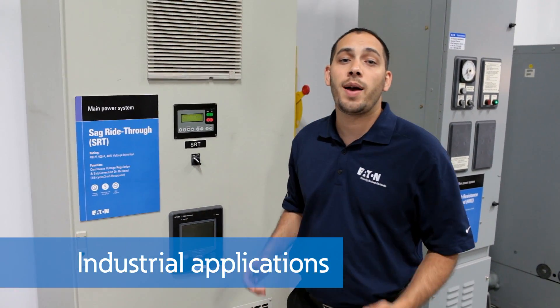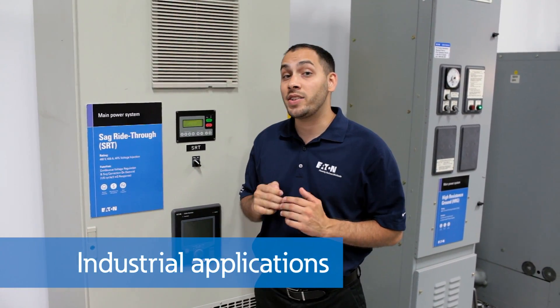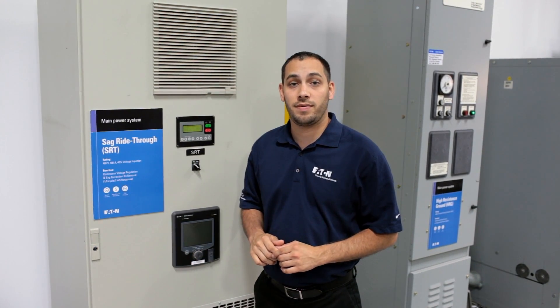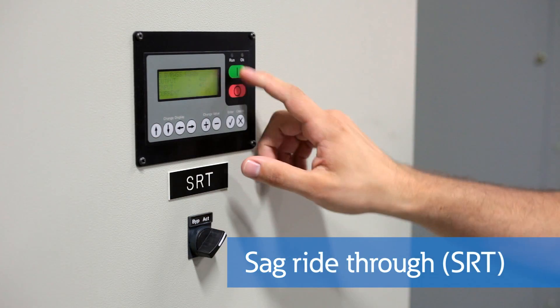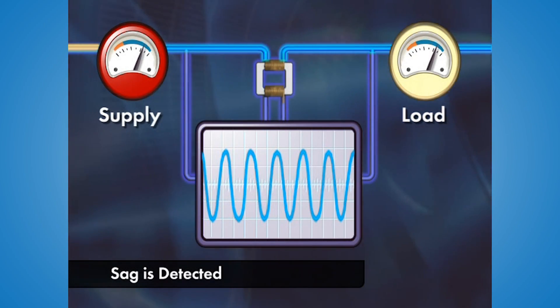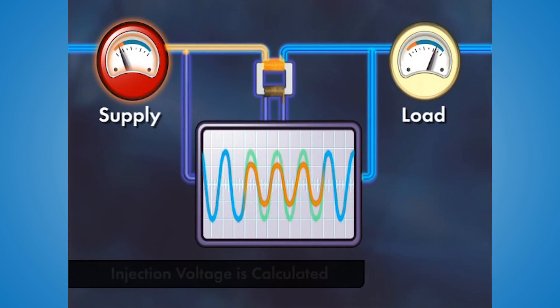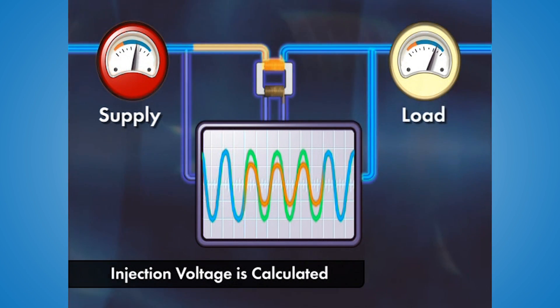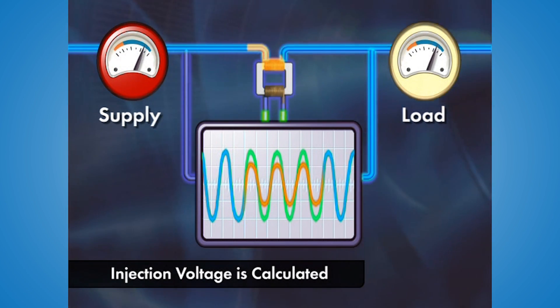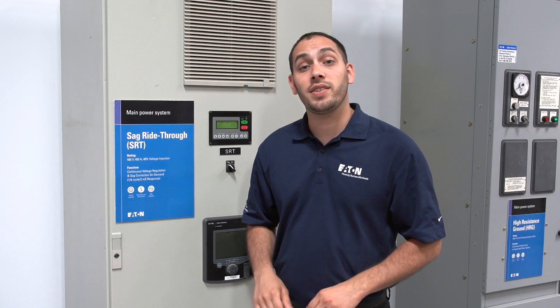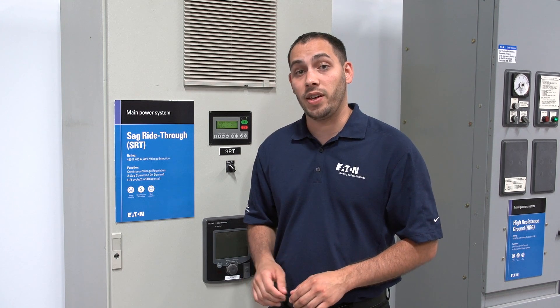For industrial applications where batteries may not necessarily be appropriate, there are other methods of sag compensation. An SRT, or sag ride-through, continuously monitors the incoming voltage and, in the case of a fault, injects the required compensating voltage into the system so that the downstream devices see an acceptable voltage level. An SRT is considered a system solution to protect many loads or the entire facility.